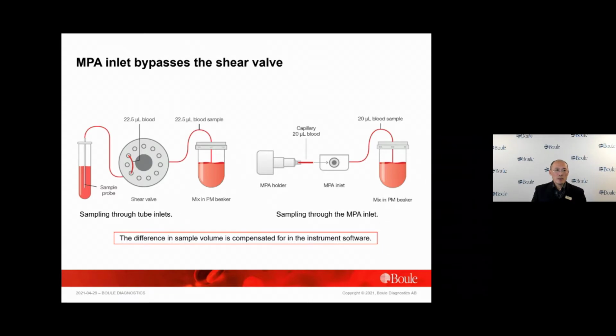We put quite big emphasis on the MPA inlet, since it is both convenient and also unique for the Boule three-part instrument. And here you can see the open tube inlet measuring the whole blood volume by shear valve from a sampling tube, either from the open tube or from the closed tubing models, such as the cap-piercer model or the walk-away sampling model.